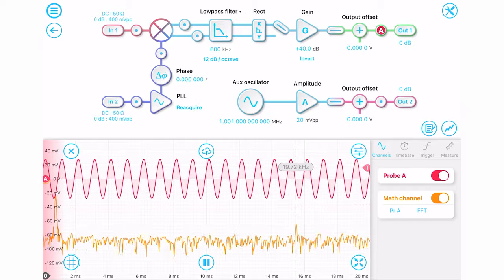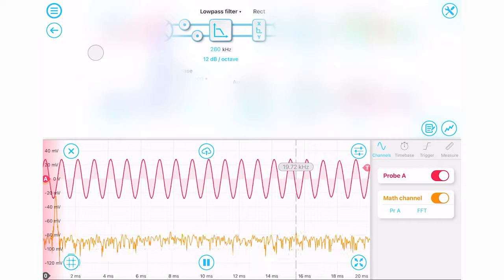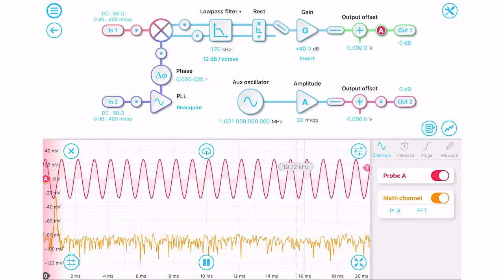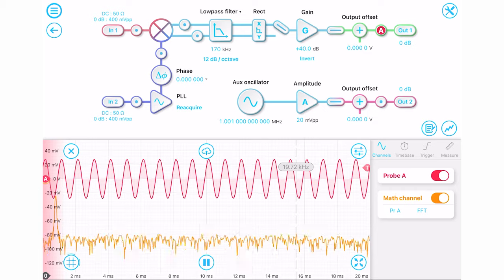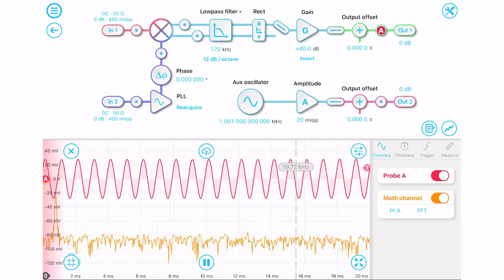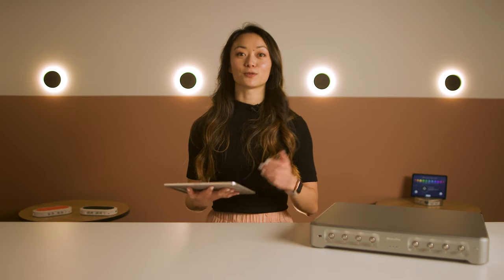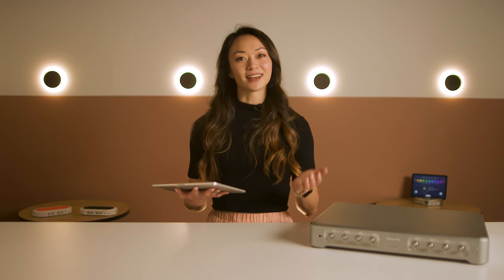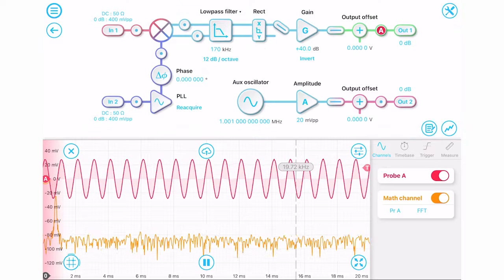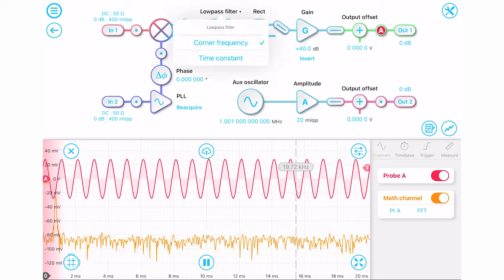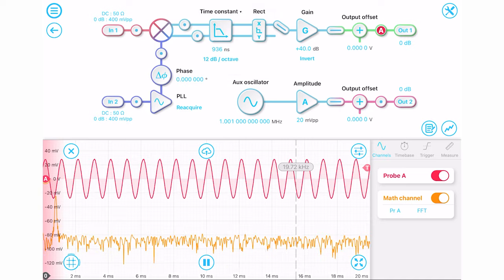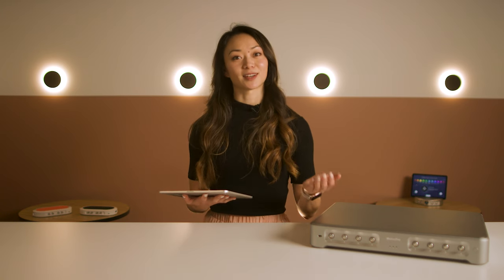We've also placed probe points throughout the lock-in block diagram view. The built-in oscilloscope provides insight into how the signal changes throughout the signal processing chain. This helps you to optimize your measurement and simplify the troubleshooting process. For example, using the probe point right after low-pass filter, you can see how much a second harmonic is attenuated as we lower the filter corner frequency. This is equivalent to changing the time constant.